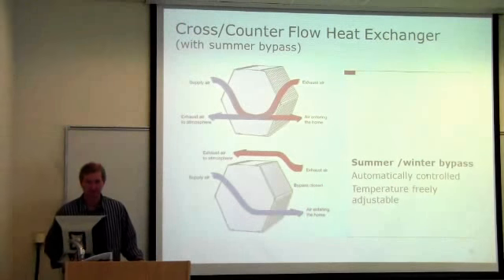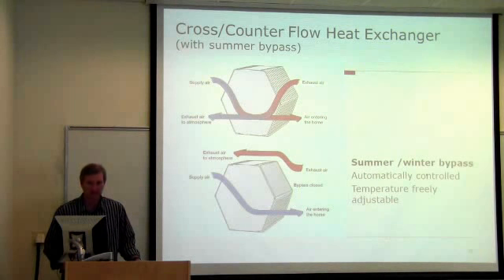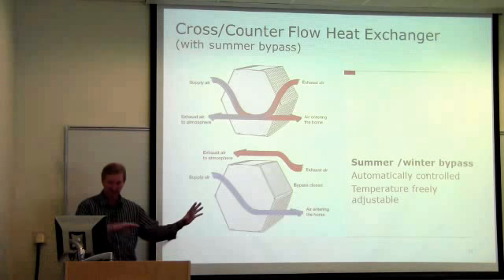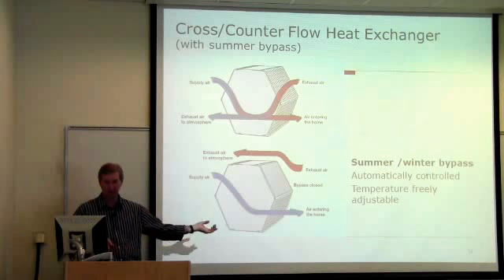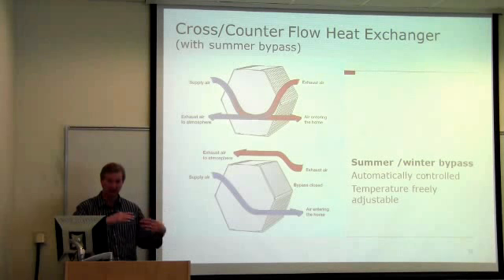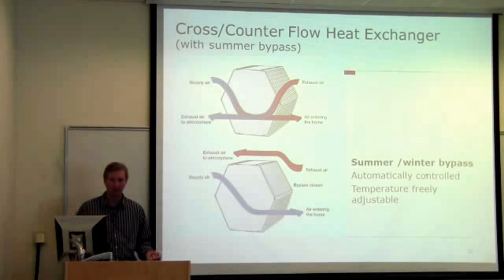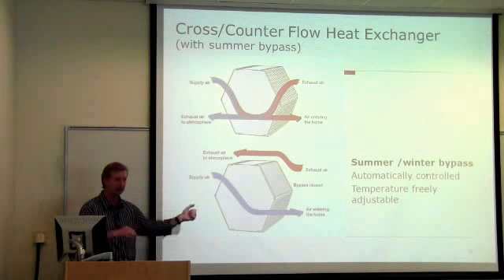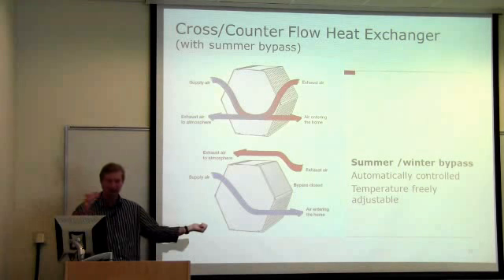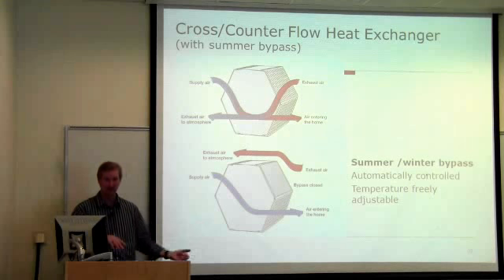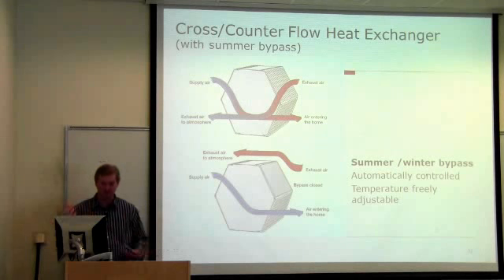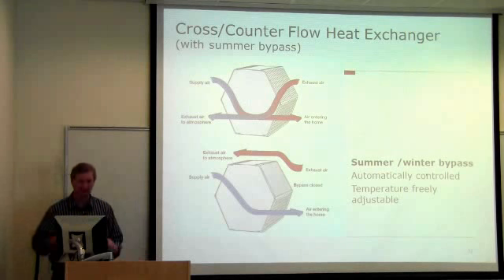Has there been any automation incorporated to, like, when the house is fully empty, you just shut everything off, like an occupancy sensor or something like that? It has automatic where you can program, like if normally people aren't home during the day, it'll drop down to level 1, like a 7-day, 24-hour program. And if you're on vacation, you press the vacation button, it drops down to 15%, and it turns over a little bit of air during the day to keep it somewhat fresh.